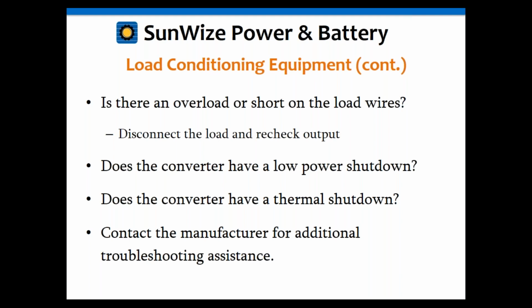Thermal shutdown, that's another one as well. That's a big problem with both inverters and converters, especially if they've been placed in a sealed enclosure and don't have proper ventilation, or proper heat sinking on a converter maybe. So again, you might want to check for that. And there might be error codes or LEDs on that device that might tell you that. And lastly, always contact the manufacturer for additional troubleshooting assistance, or check the manual. The manual might have some troubleshooting instructions in it, so you might want to check that as well.